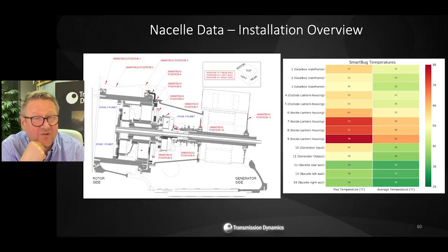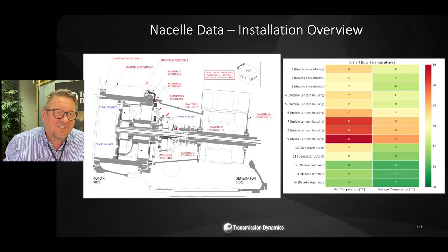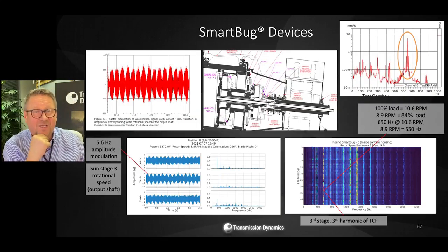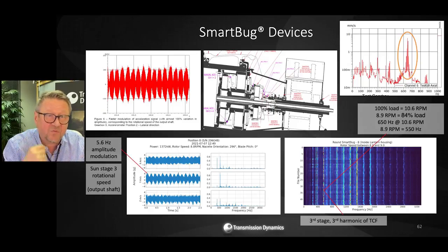You can see on this occasion the red arrows showing locations and positions of the bugs, which were strategically positioned to be effectively adjacent to the existing sensors, so we can correlate the data between the existing sensors too. And here we are. We've got the SmartBug data on the left-hand side. You can see the very strong amplitude modulation. You can see the tooth contact frequency being a carrier frequency modulated with a modulation index nearly 100%. And then when we look at the frequency spectrum on the right-hand side, you can see those sidebands, and on the left-hand side, you can see the amplitude of modulation, which is occurring on this occasion at a frequency much lower than the carrier frequency, 5.6 Hertz.